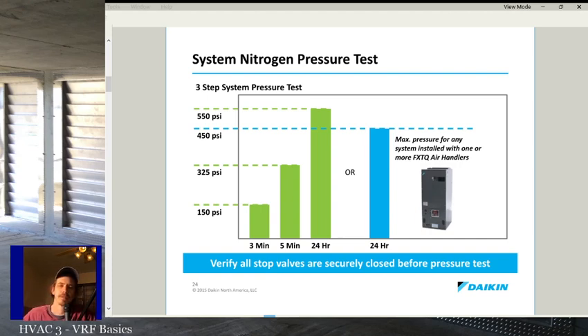After you're done brazing, you want to do good leak detection. And good leak detection is putting the system under a pressure test for as long as possible. It is extremely important when you're dealing with a system with a lot of joints that you do the best possible job on checking for leaks. And a VRF system is a very good example of a system that's going to have a lot of joints. But again, if you're doing a commercial split that just has a long run with a lot of fittings, it's the same principle. Every joint's going to have some amount of leakage to it.